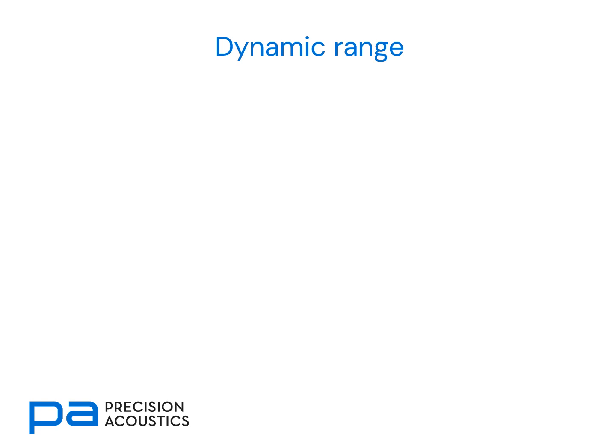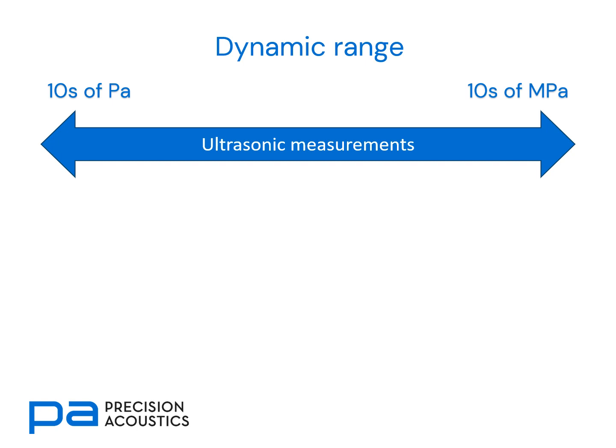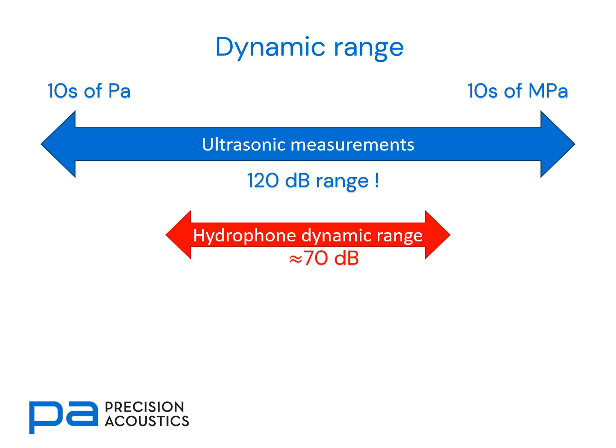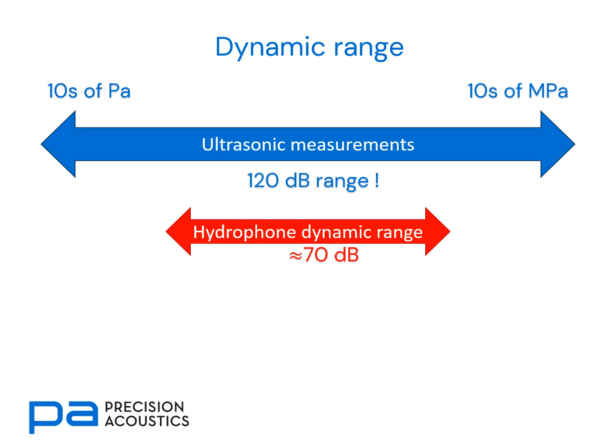The first thing we need to consider is dynamic range. Ultrasonic measurements can often be conducted anywhere between tens of pascals and tens of megapascals, although rarely that entire range within one measurement. This is in excess of 120 dB dynamic range. If we compare this with the typical hydrophone measurement system, which has a dynamic range of approximately 70 dB, we know that we then need to optimise whereabouts our hydrophone's dynamic range sits within the possible measurement range.